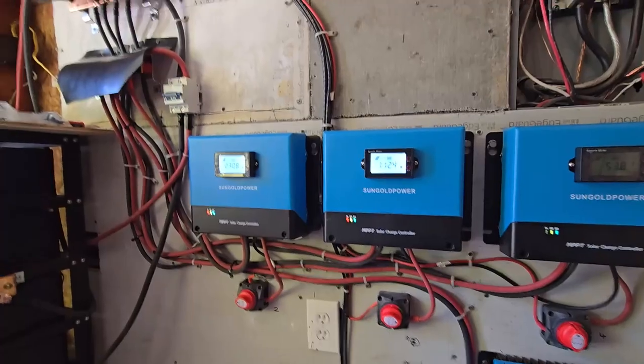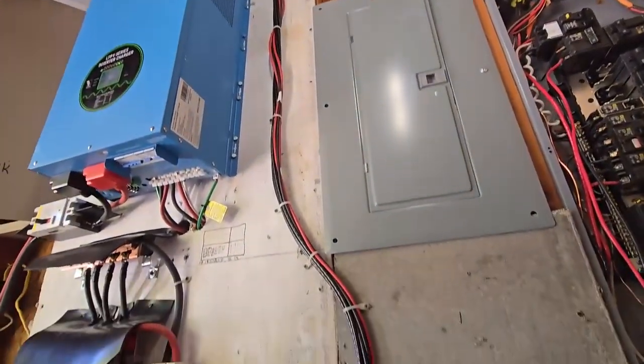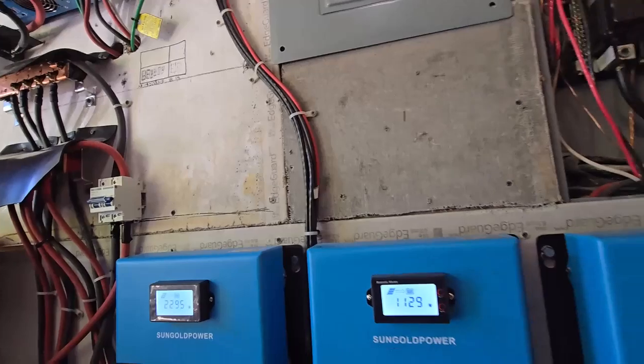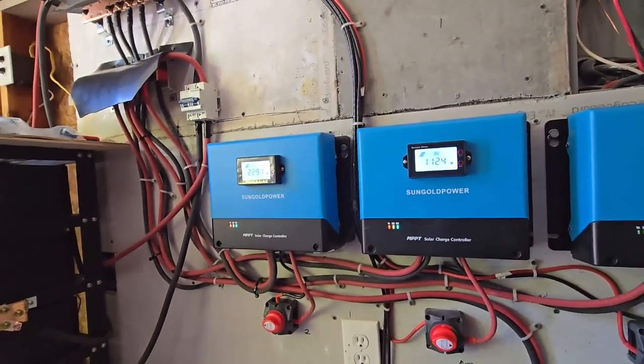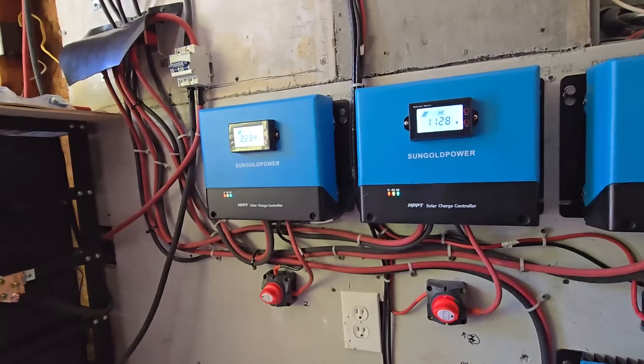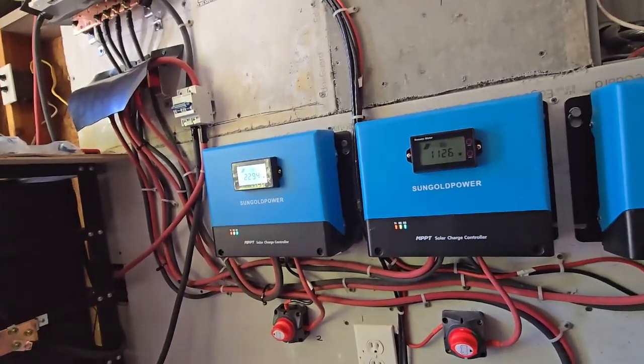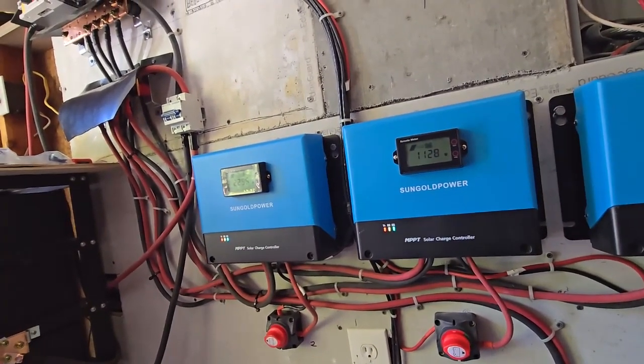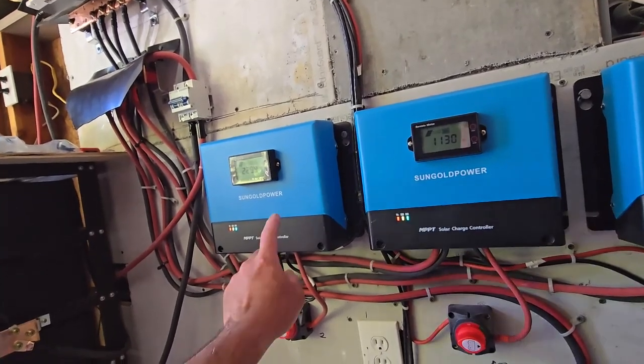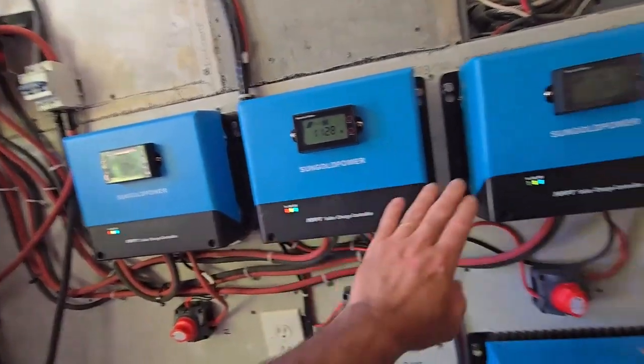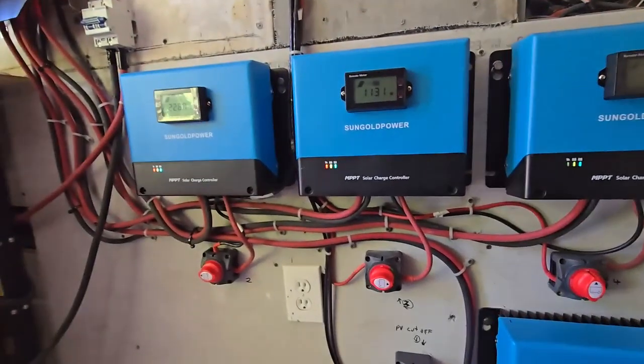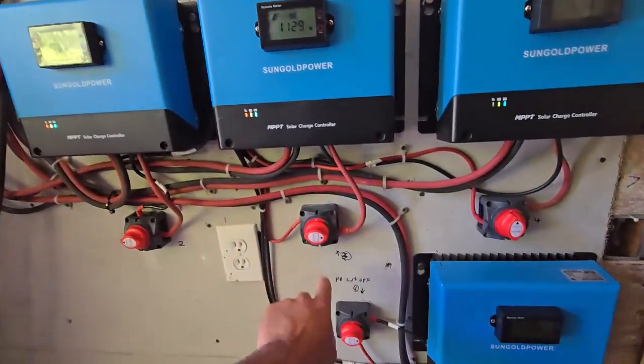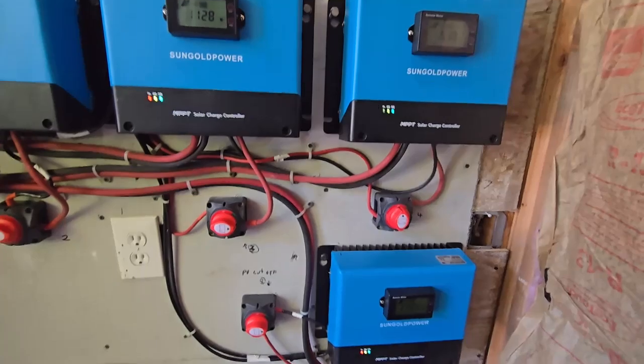All right, so from the roof, all our cables come down. These are the PV cables that come down to the combiner, or from the combiner boxes to the charge controllers. So the negative side for each one, each combiner box, come out of the combiner box with one set of PV cables. The negative goes directly into the charge controllers. The hot side goes into these, so I can shut them off.